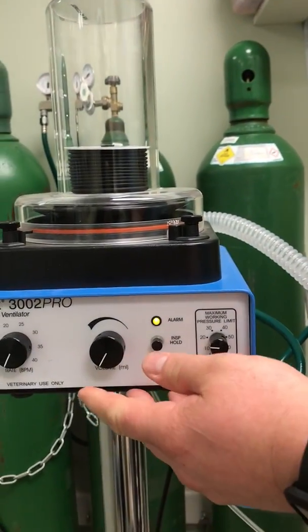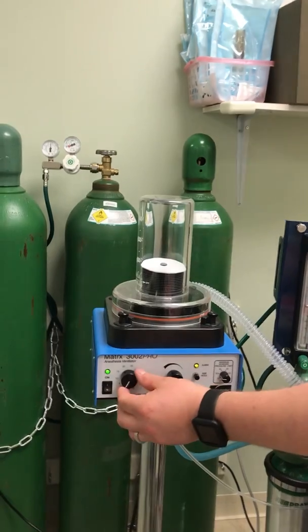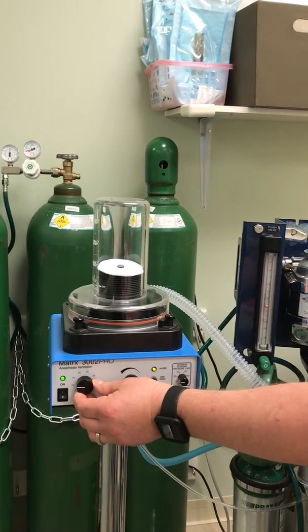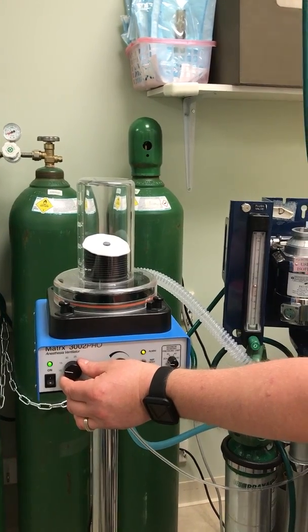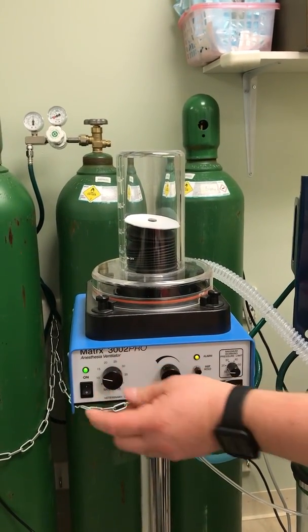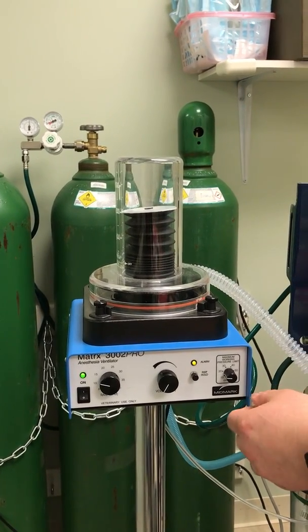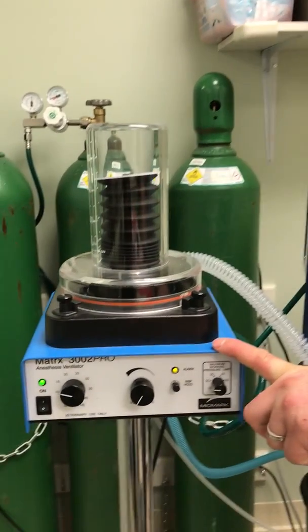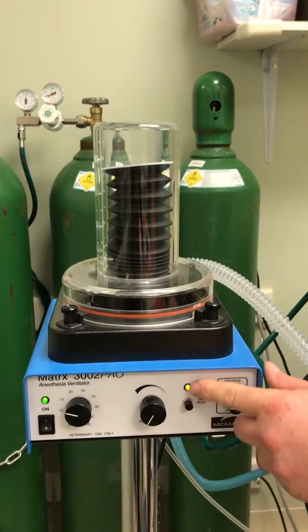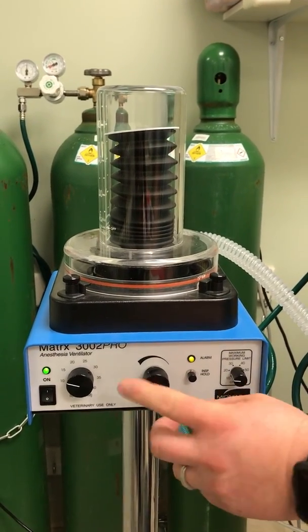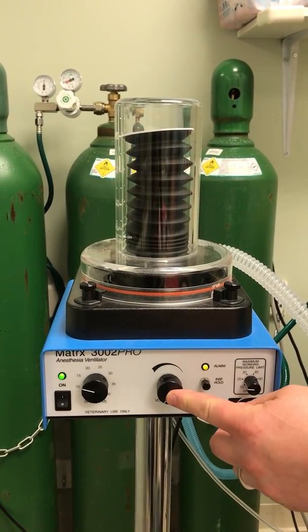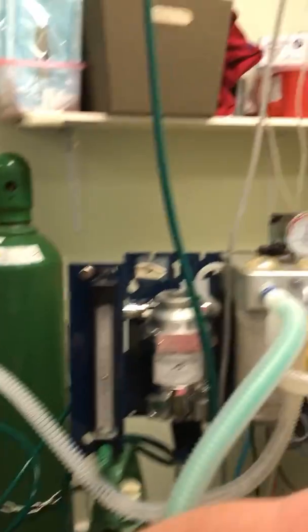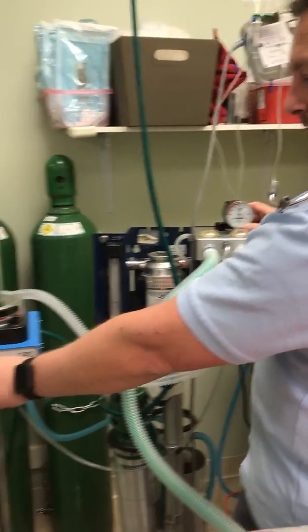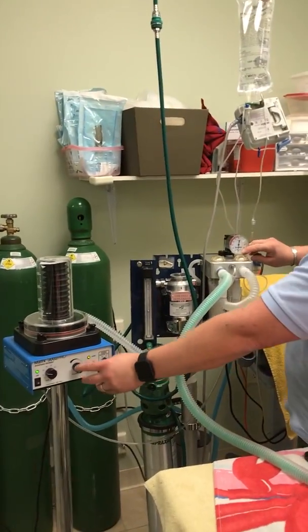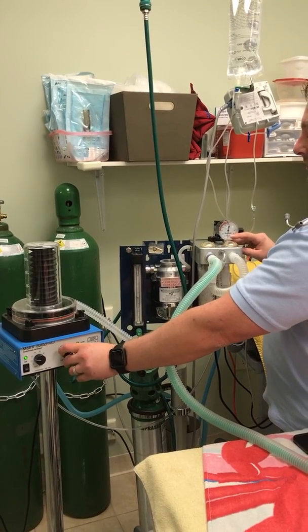And then we're going to do 2 things. We're going to increase our respiratory rate, and the rate should be somewhere around 12 to 15. And so that'll drive how fast these bellows are going. And now we're going to get our pressure adjusted so that we're getting a normal pressure and we're not getting the low pressure alarm. The way we do that is by adjusting the flow meter and at the same time watching the pressure gauge on our anesthesia machine. So currently it's about 2. We're going to want to see this number increase to about 12.